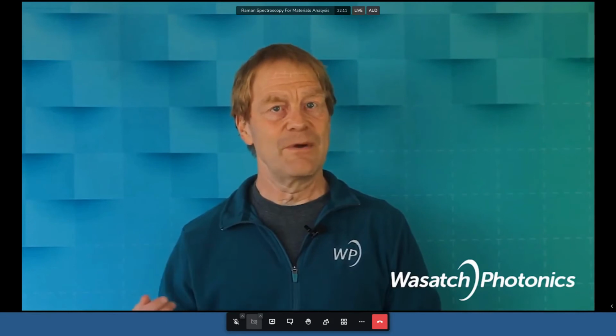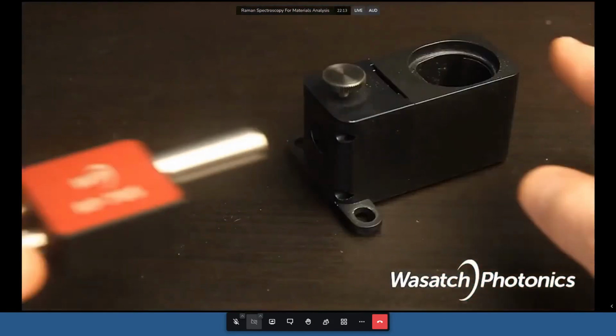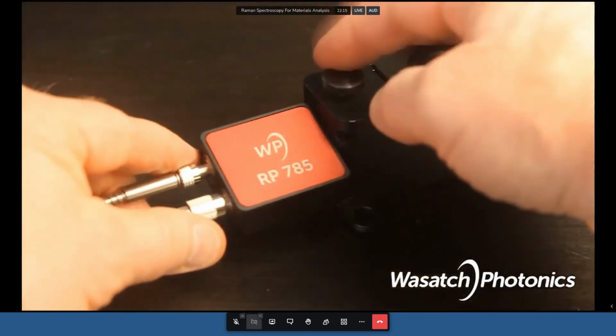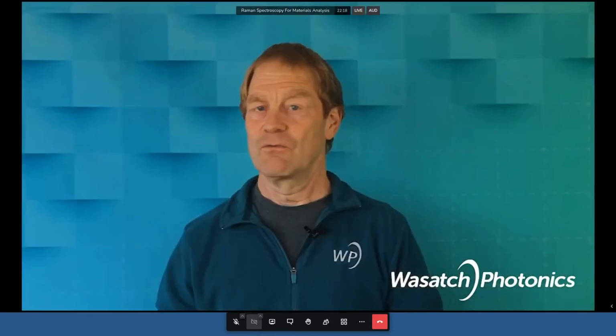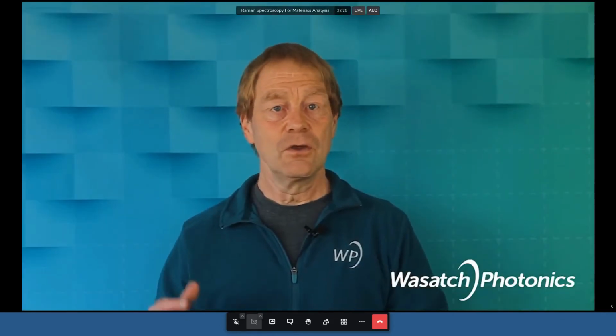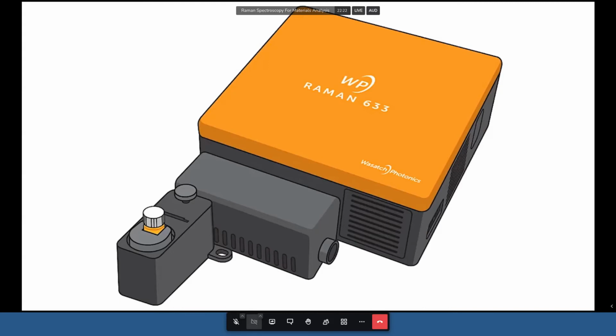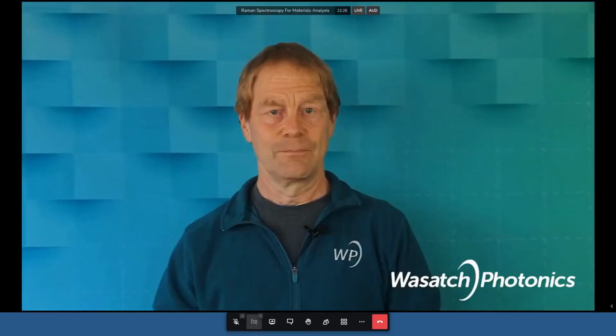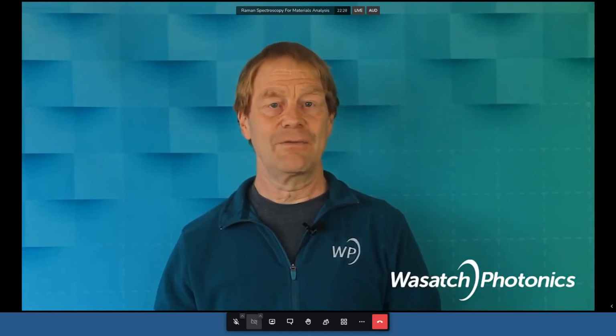Finally, we insert the Raman probe into the sample holder. Push the probe all the way into the sample holder and lightly tighten the thumb screw. For the fully integrated systems, you need to push the sample holder over the front lens of the spectrometer and lightly tighten again the thumb screw. That was it for the optical side of things.